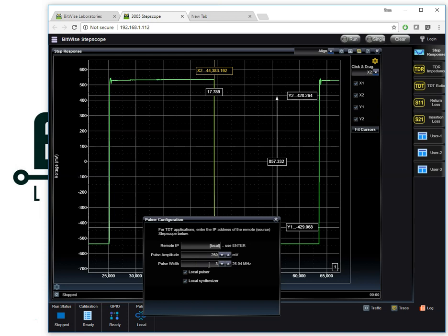For example, if you're measuring short cables or short distances, you might set this to a fast pulser. But if you have to look at very long reflections, of course, then this pulser would want it to be much more spaced out. Longer pulsars take more time to capture their waveforms. So that's the trade-off you'd make.